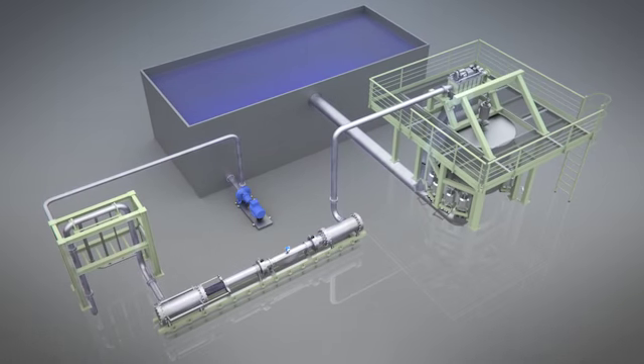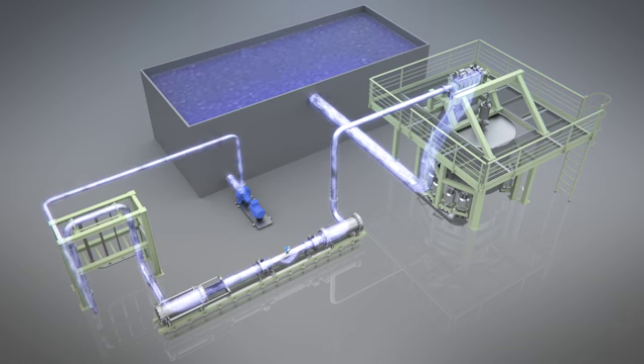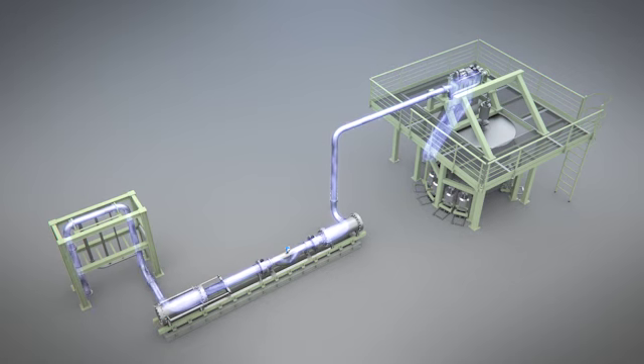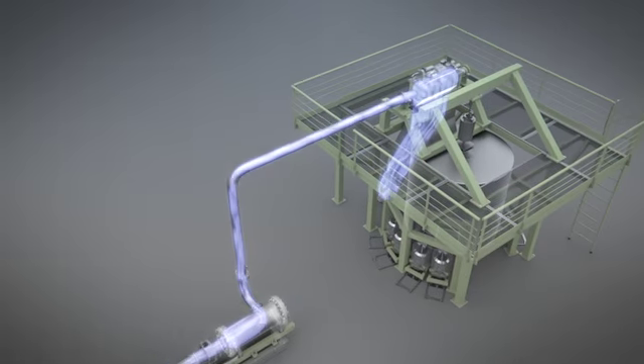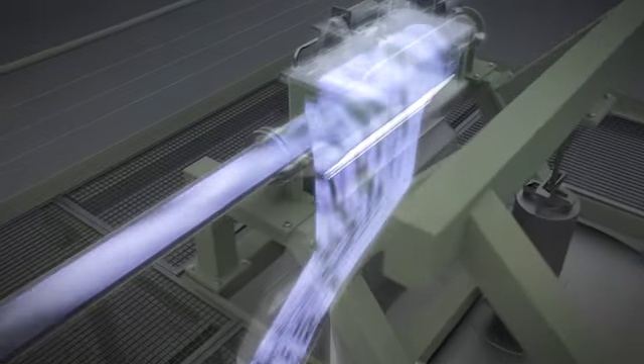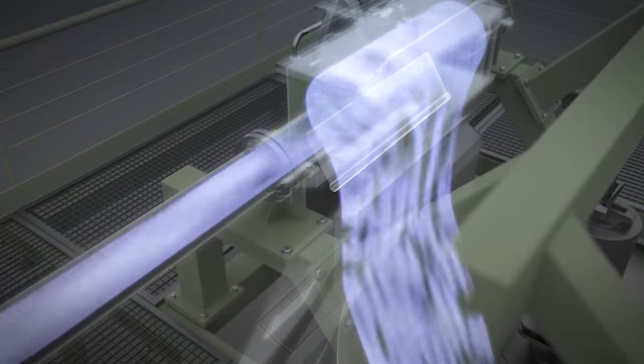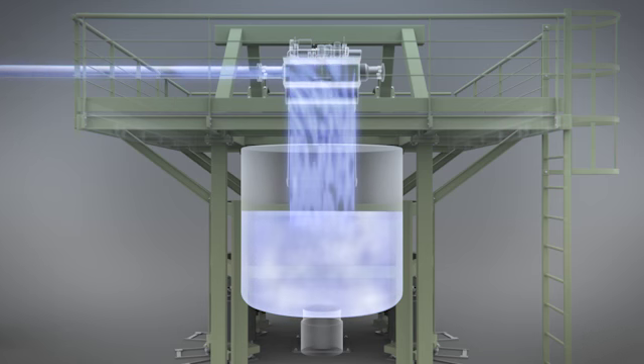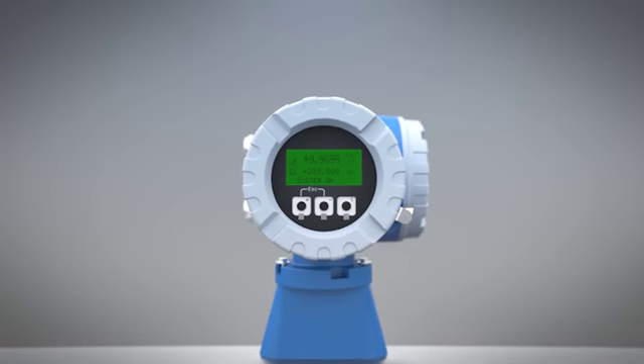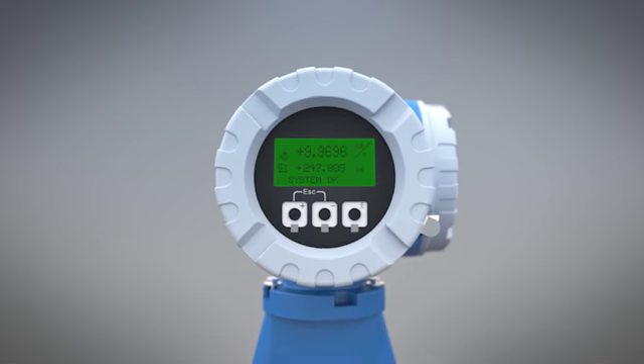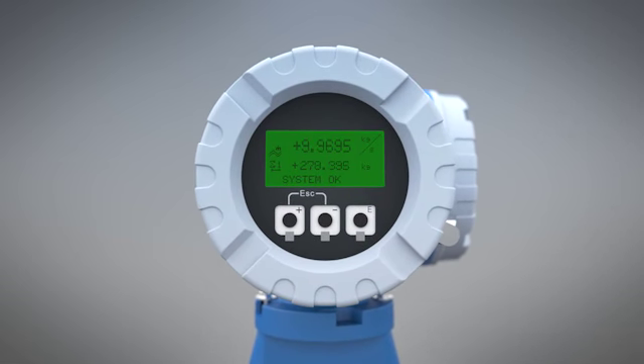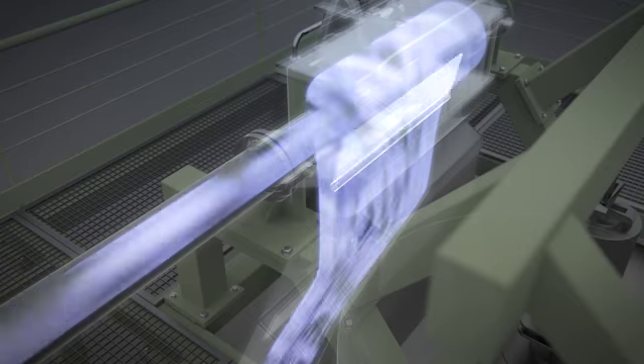The calibration process begins as water is fed through the system and adjusted to the desired flow rate. Once the correct rate of flow has been established, the calibration measurement can begin. The water stream is then diverted at high speed into the weighing container, while at the same time, the plant control system activates the electronic flow counter of the device under test. At the end of a previously defined time period, the calibration measurement is terminated and the flow of water into the weighing container stopped.